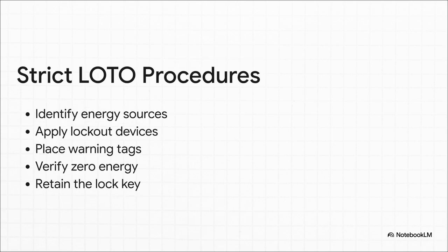Now, beyond what you wear, it's about what you do. Electrical safety is still a massive concern, which means strict lockout/tagout, or LOTO, procedures are completely non-negotiable. It's a rigorous process. You systematically identify all electrical energy sources, lock them out with designated devices, and apply warning tags with your name and the date. But you know the most critical step? Using a certified voltage detector to independently verify a zero energy state. Oh, and the technician has to keep that lock key in their pocket the entire time.